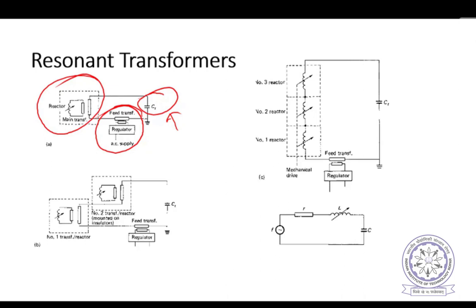But connecting an inductance in the high voltage circuit and changing it there is ruled out. So what is done is a transformer is used. On the transformer primary side you connect a reactor. Obviously it will reflect at the secondary side. Impedance transformation you may be knowing. So on the primary side we connect a small reactor at low voltage level, and we can change the reactance at the low voltage level, and that will automatically get reflected in the secondary side. We don't even have to touch that one.